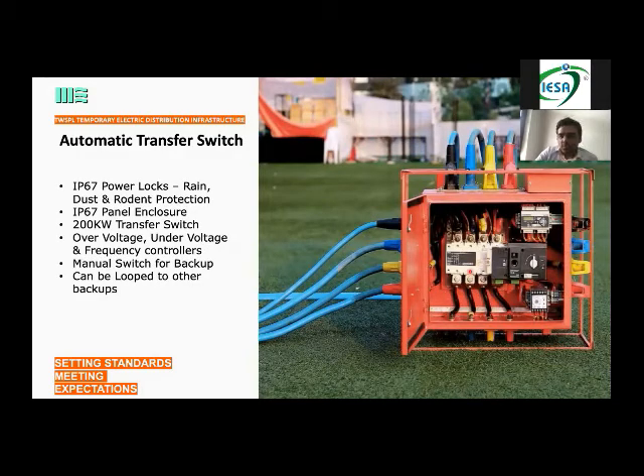With this automatic setup, there is one more important thing: the automatic transfer switch. The company claims that nothing is going to happen. There is a warranty and everything. If by chance the automatic transfer switch doesn't work, there is a manual switch also given over here, which can shift the power manually, in case, maybe 0.001% of the time, the automatic transfer switch doesn't work. So this is what an automatic transfer switch is. Again, we're going to talk about what IP67 is and what power locks are, but it has to be totally enclosed, because most of the time the automatic changeovers or the manual changeovers are kept outside on sites.